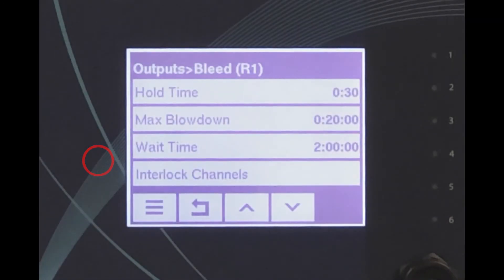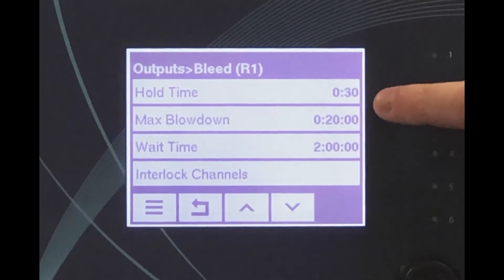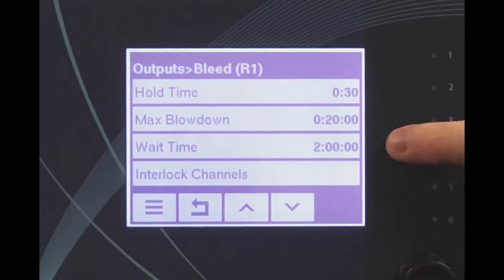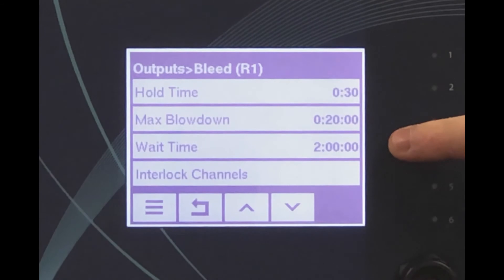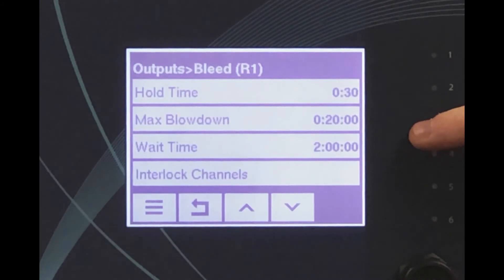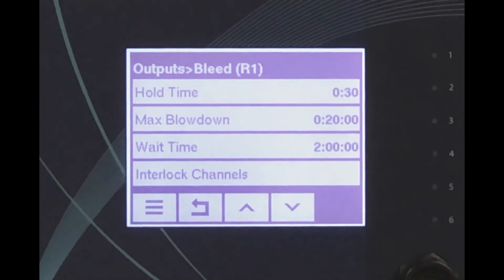Trapping and blowdown will continue until the trap sample reads below the set point. At that point, the controller will wait for the pre-programmed amount of time — sometimes called the interval time or wait time — before once again sampling the boiler. It is important to note that the conductivity measurement is not updated during the wait period, since the sensor is no longer seeing a fresh sample of boiler water.